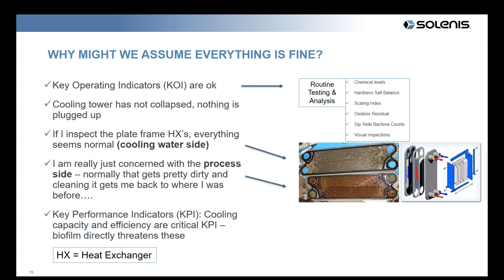So if you look at this slide here, and this is actually a slide of one of our targets for our device that we'll be talking about in just a little bit here. And you can see that that's 250 microns of biofilm. And we wiped it away like it's nothing on the right half of the one picture. But that's 250 microns of biofilm, which is 10 times thicker than what's robbing you of 5% of your heat transfer. So you can see that if that was 10 times reduced in thickness, you might not even be able to see it.